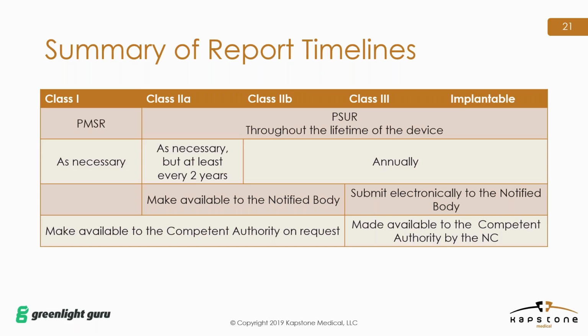category. So class 1, if we're looking on the left-hand side, class 1 requires that post-market surveillance report. It's updated as necessary, and it's made available to the competent authorities on request. So there's no notified body. They can request it, of course, but it needs to be made available to the competent authority at least. Then you have your class 2A, 2B, 3, and implantables. They require that periodic safety update report. It's required to be done throughout the lifetime of the device. Reporting requirements do differ between the lower of the high risk class, I guess the medium risk. So class 2A, you're required to update this as necessary, but at least every 2 years. The remaining high risk devices require update of this periodic safety update report at least annually.